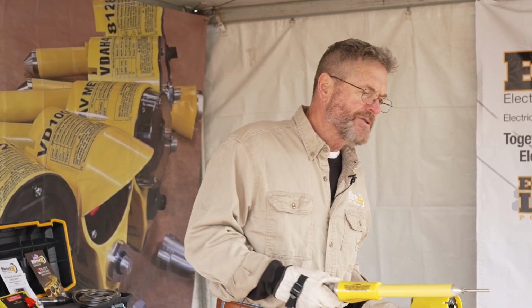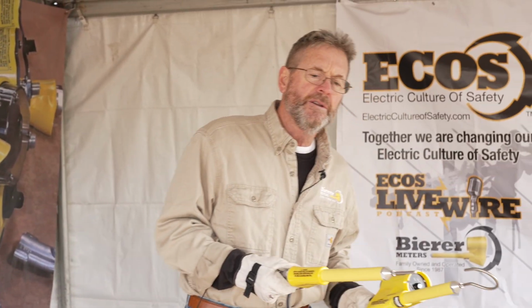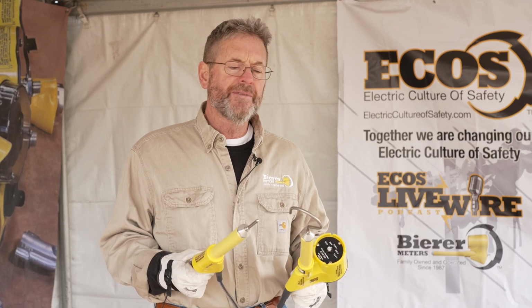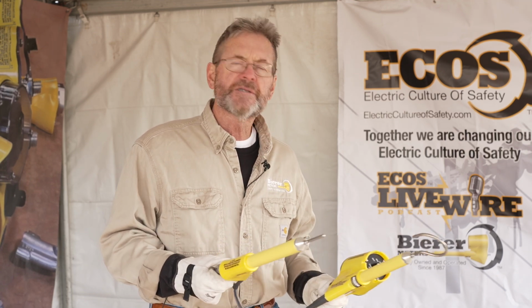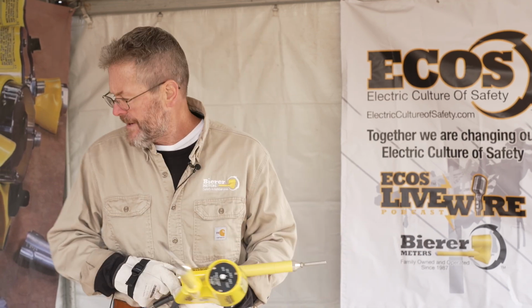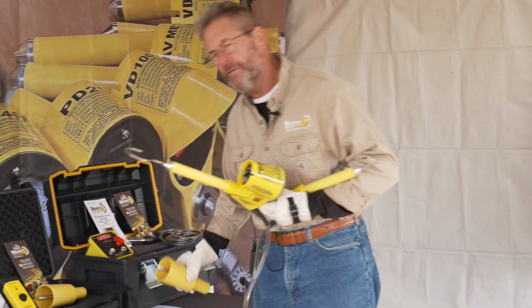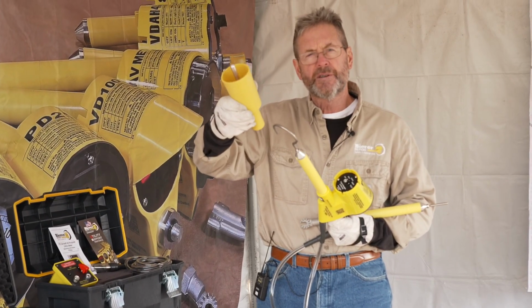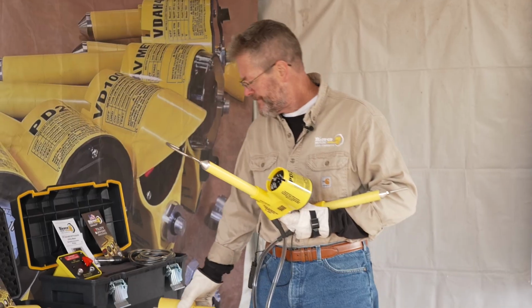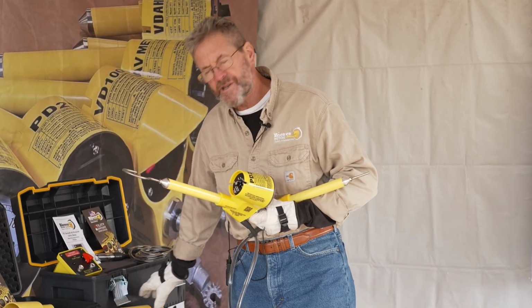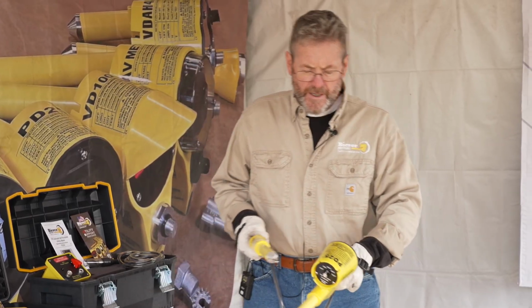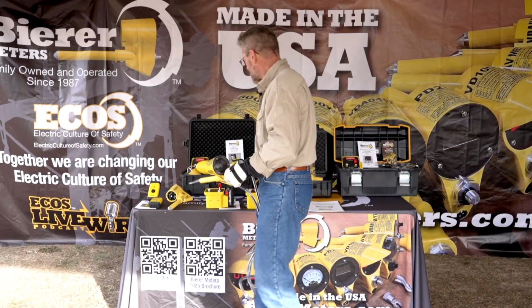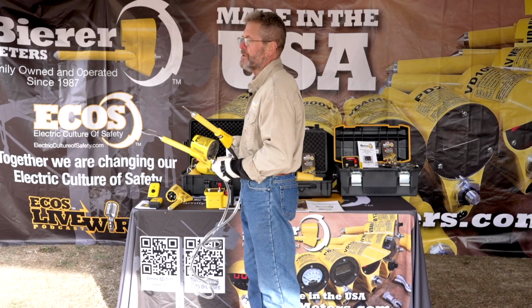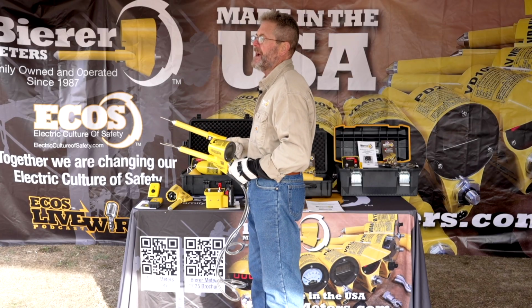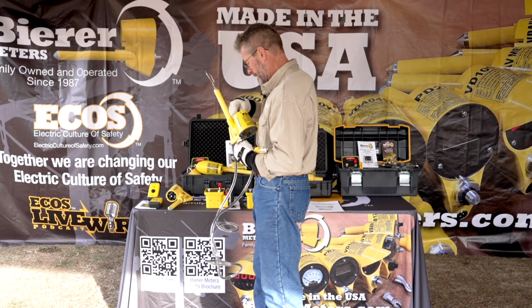A lot of times when I travel doing training, I get to a utility or a contractor, and in their barn, their tools, they don't have the proper accessories. Well, just call us, order them. We also have the bushing adapter right here. If you're going on some hot bushings, some feed-throughs, things like that, get a bushing adapter. So the corded device, 3 kV power supply, works every time. Live, dead, live test. We're ready to roll.